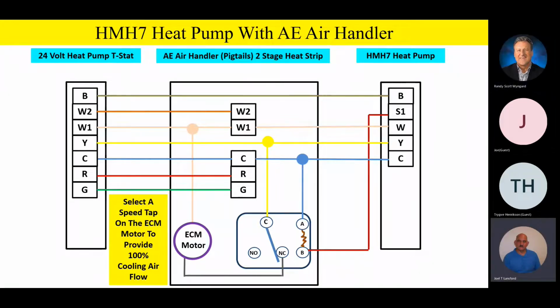Okay, excellent. So the next contact on the relay you'll see is a normally open contact. With the normally open contact, we're going to go over and select a speed tap on the ECM motor to provide 60 to 65% airflow. So that's your airflow reduction.